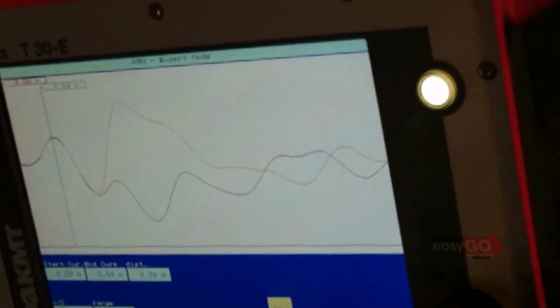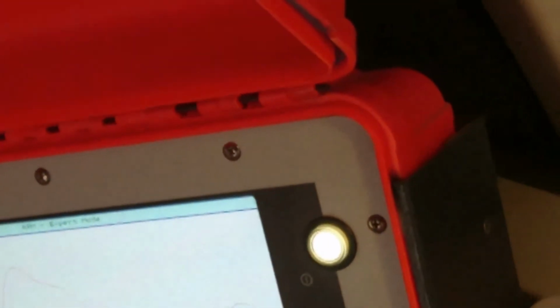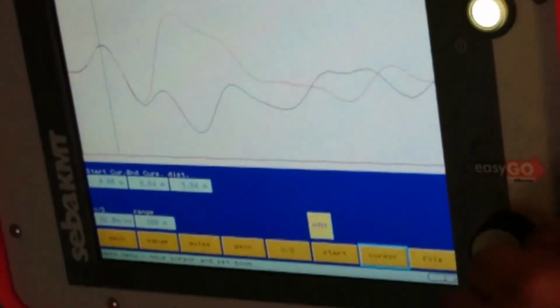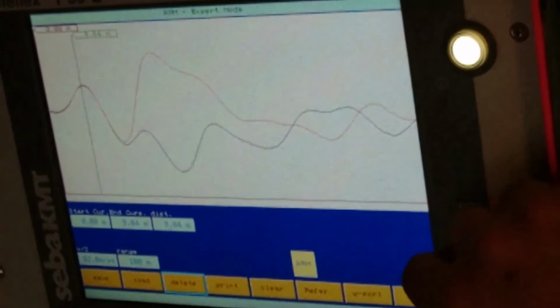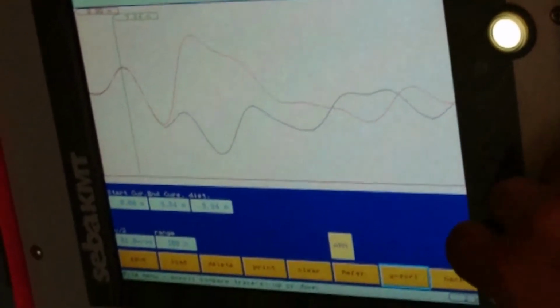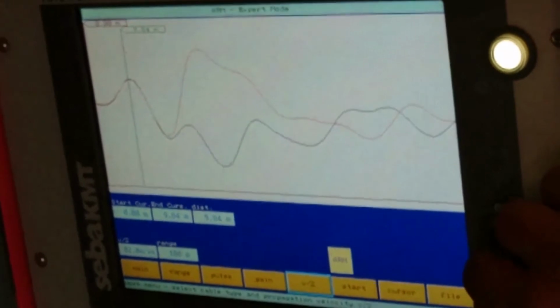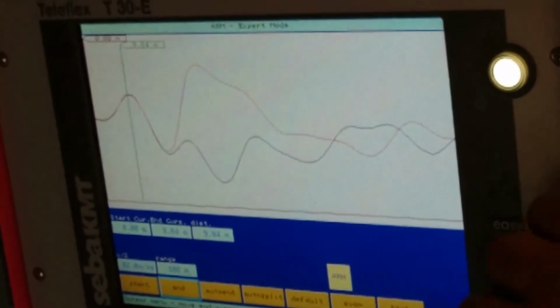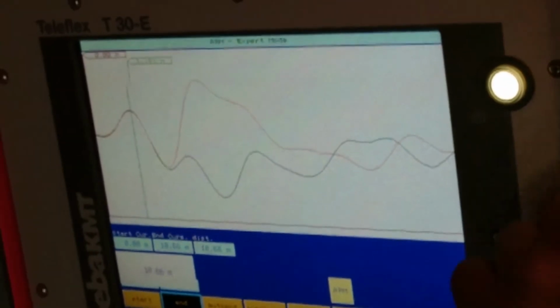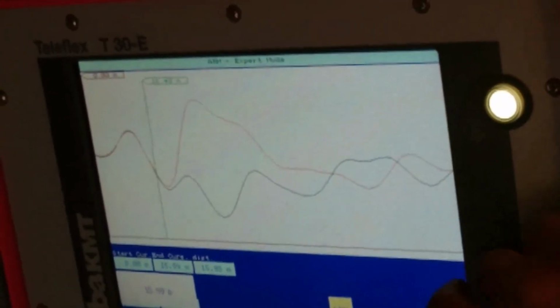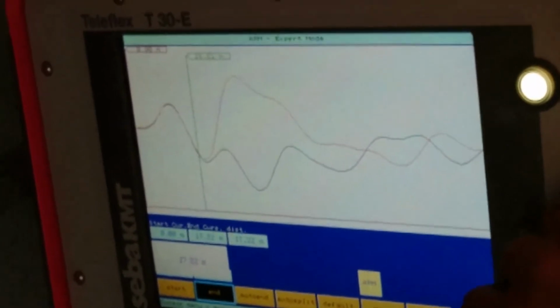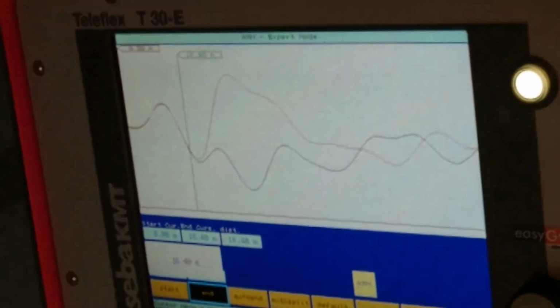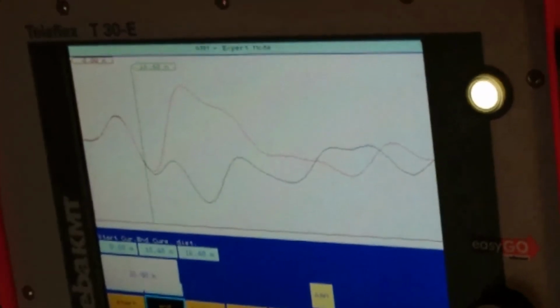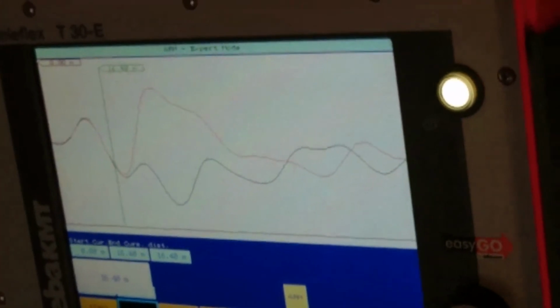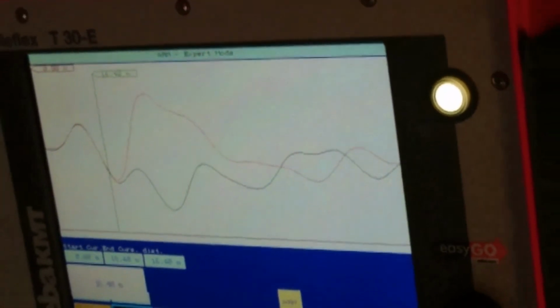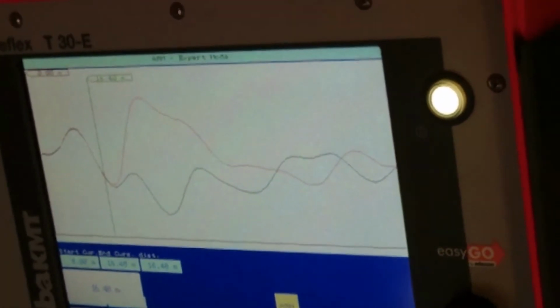If I move the cursor, I go back here. Where is it? Back. Cursor, and cursor, yes, so I move the cursor to the change point, somewhere here. See, it's telling me 16 meters, which is not correct because of the velocity factor. So now we know how much the length of this cable is, around 20 meters.